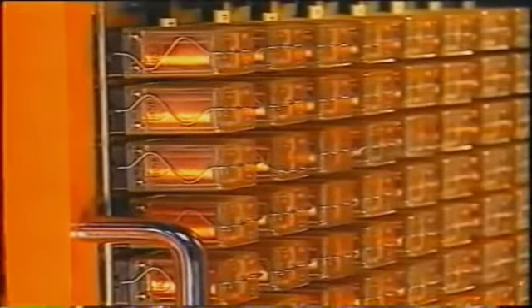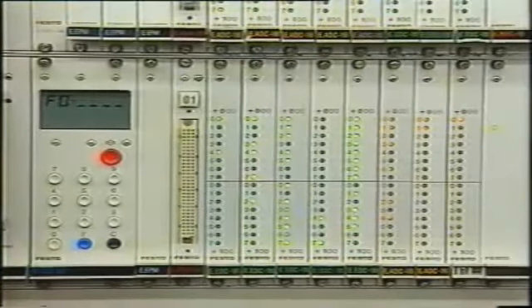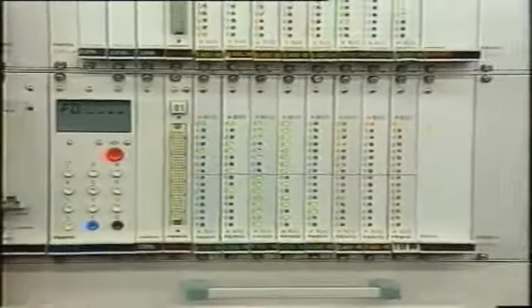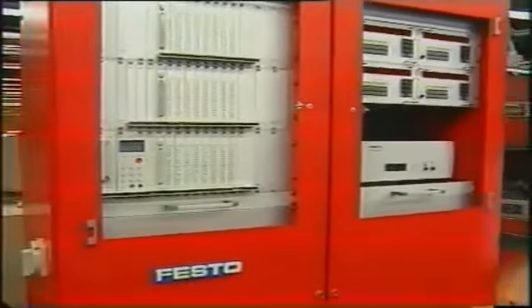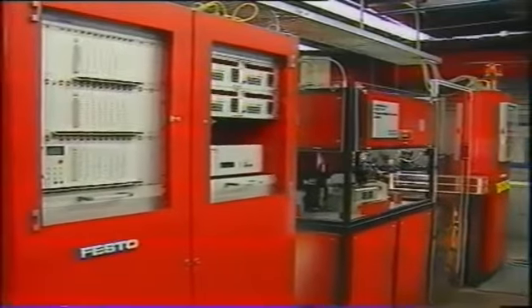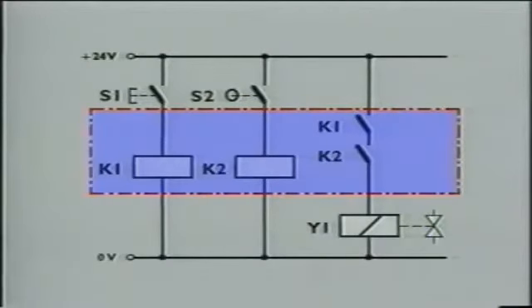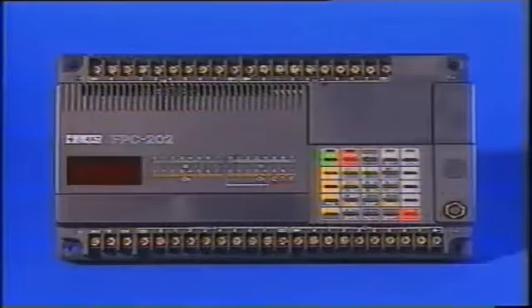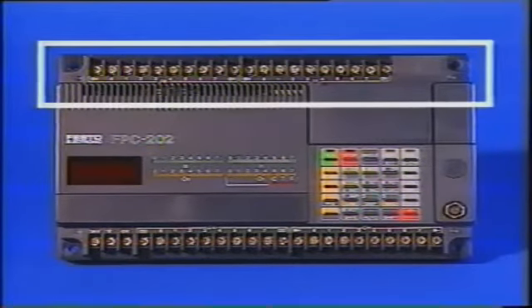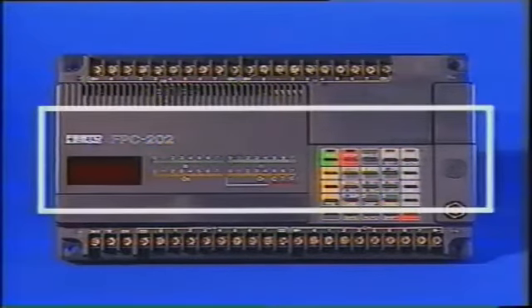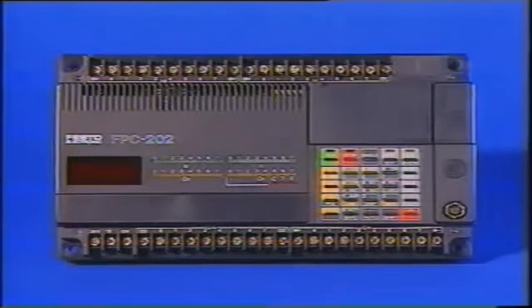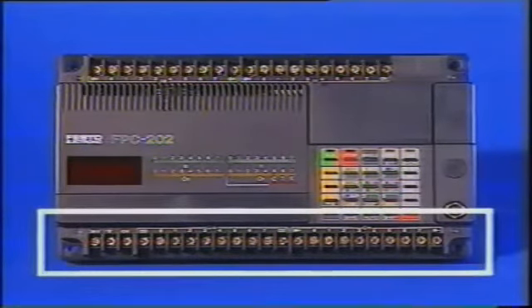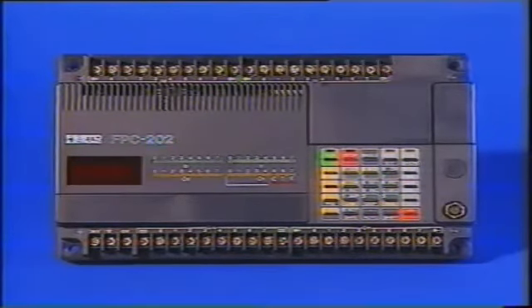The function of the wiring of this hardwired machine can also be undertaken by a programmable logic controller, or PLC. In this case, the logical association and processing of signals takes place here. The functions in the marked area of the hardwired circuit are now undertaken by the PLC. A PLC consists essentially of three parts: the signal input part, the central control unit, and the signal output part. The central control unit consists of a processor and program memory.